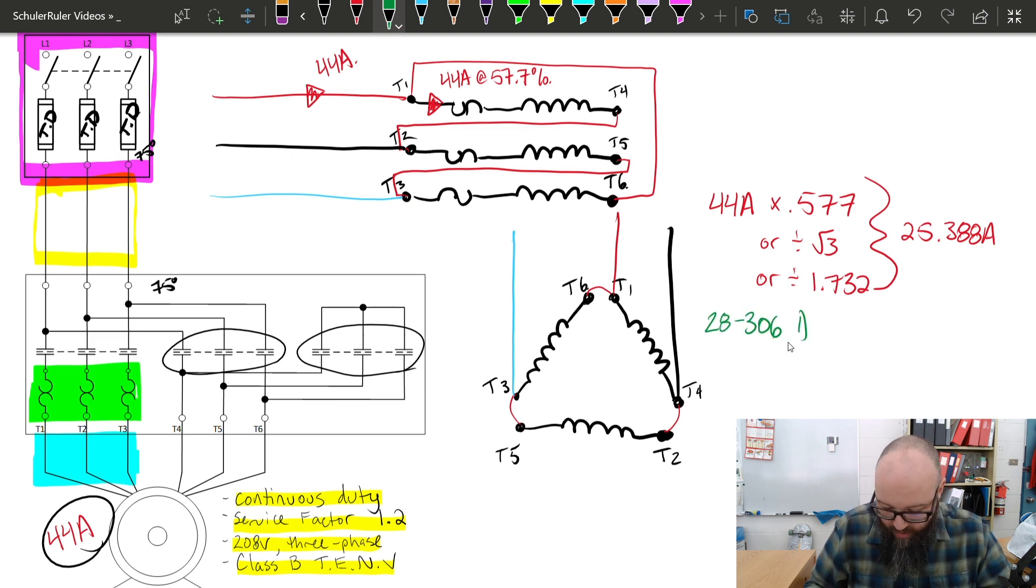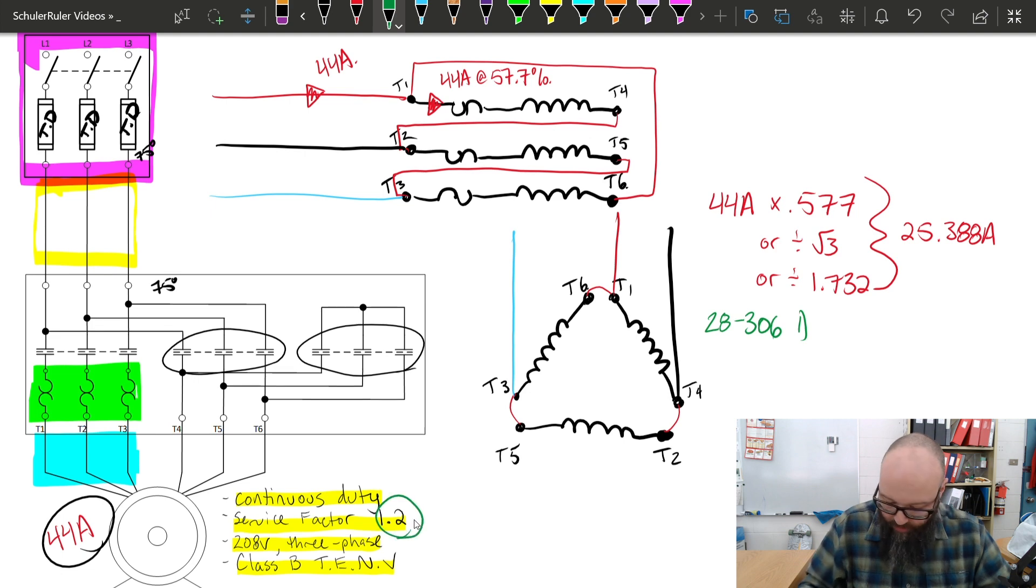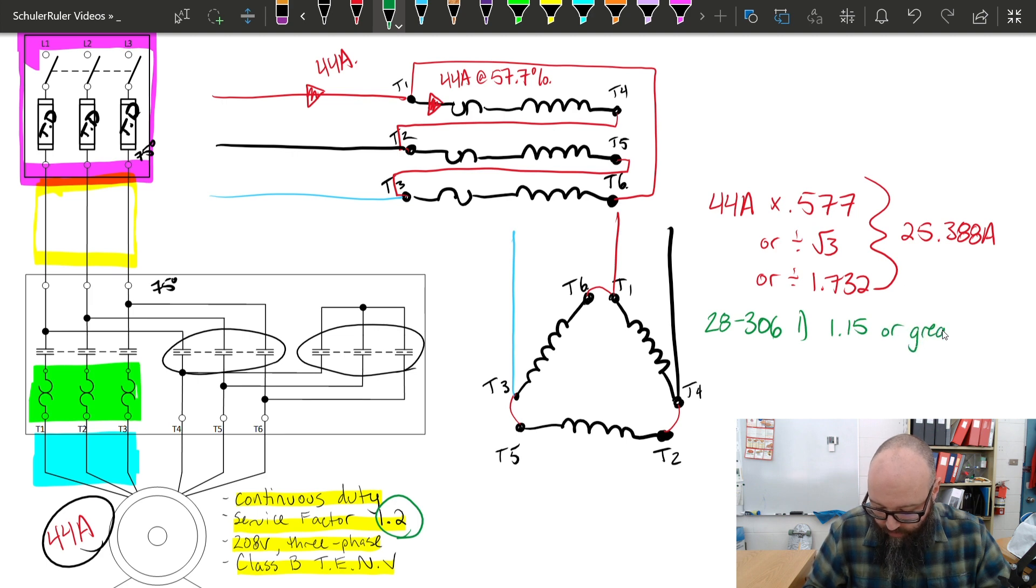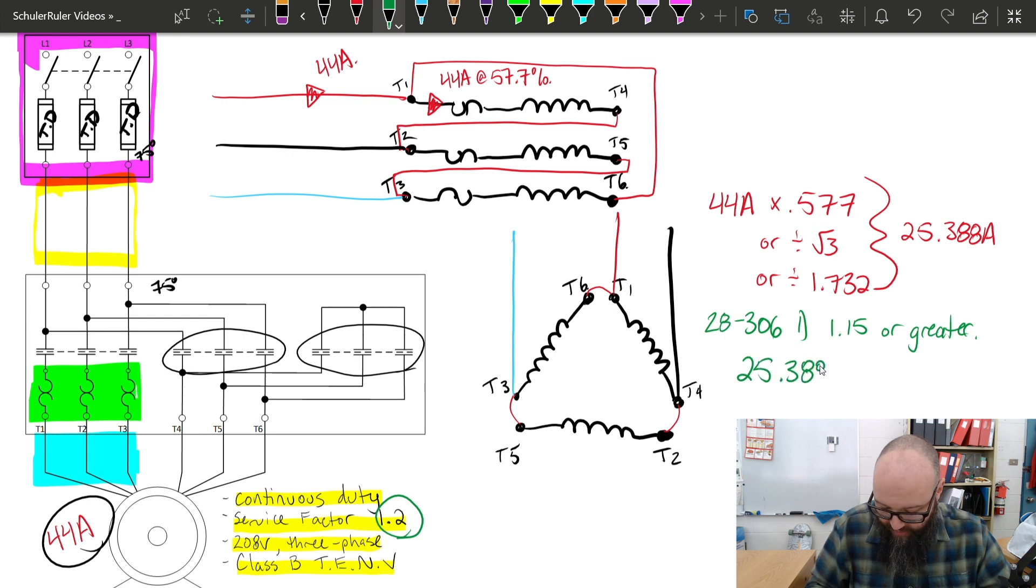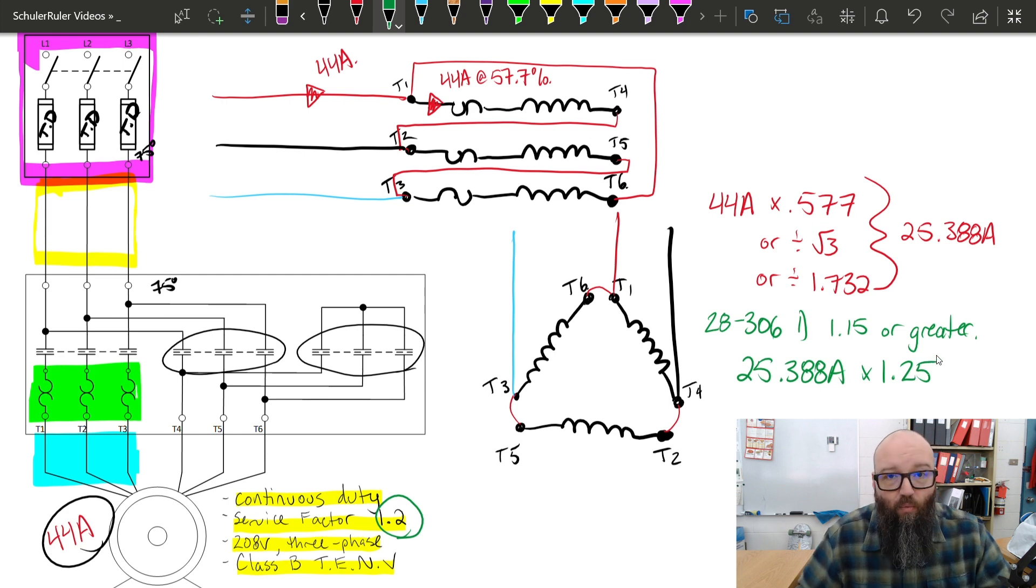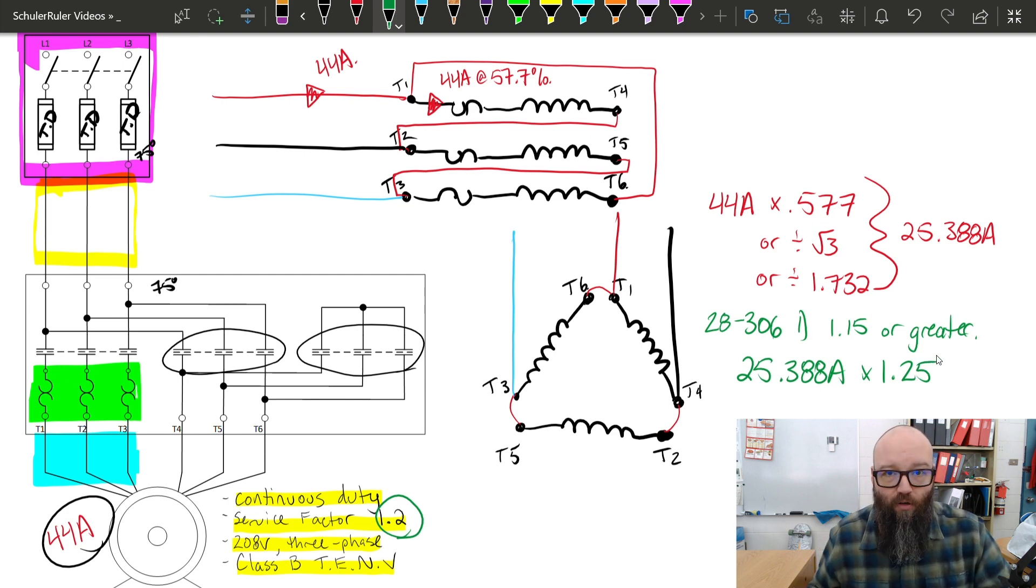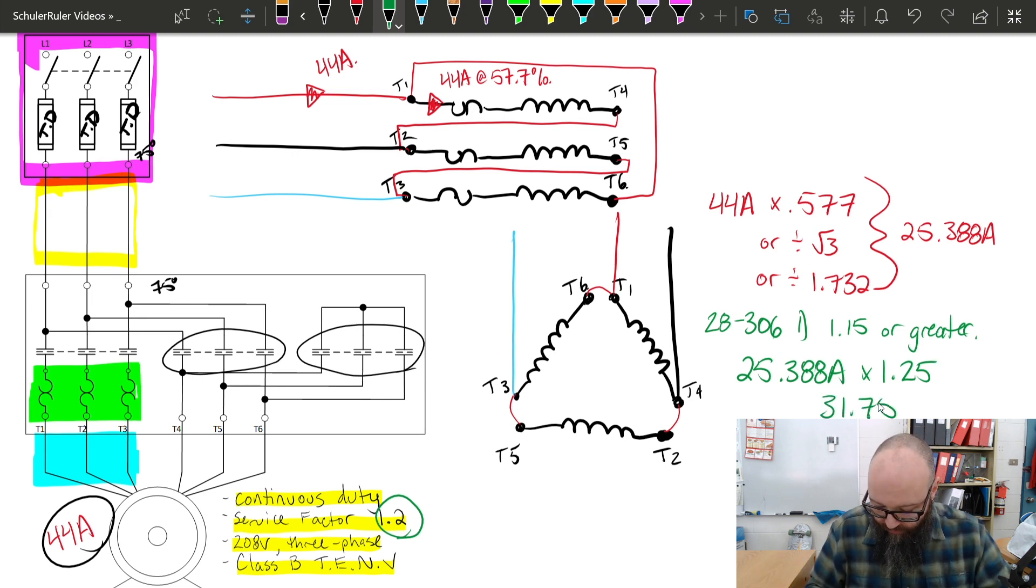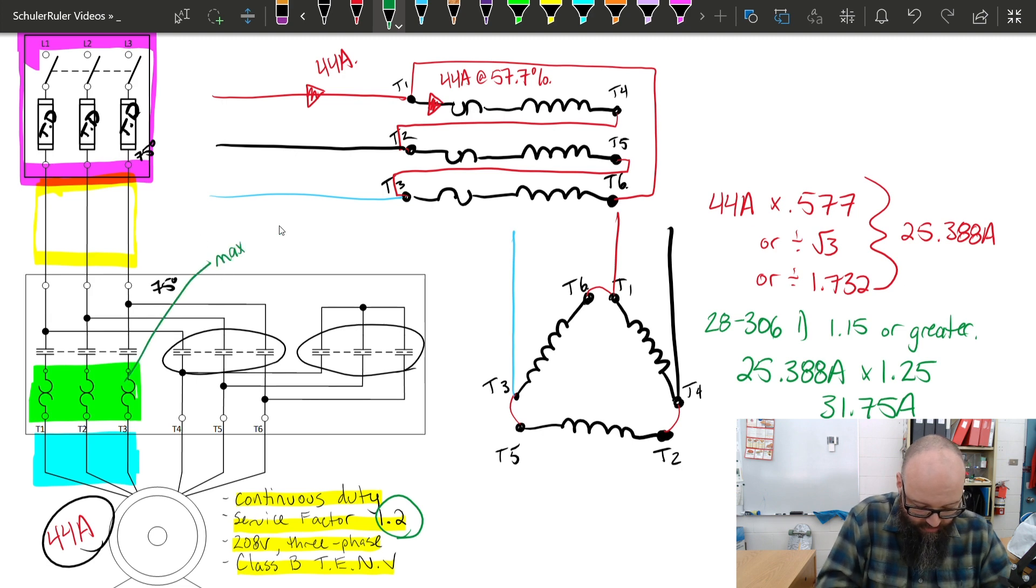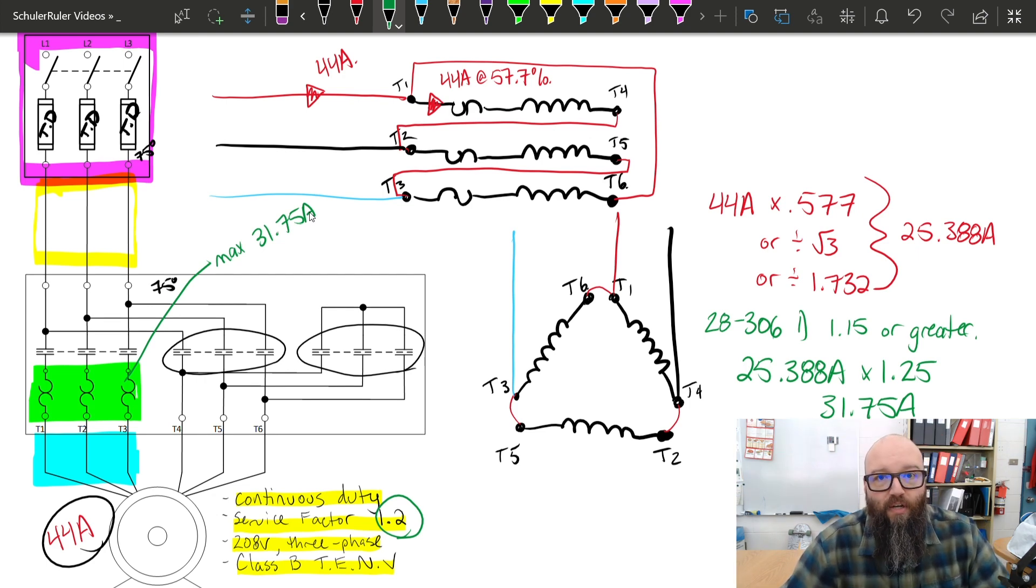Now, this is my starting point to determine the size of my overloads. This is where I'm now going to go back to 28.306 sub rule one, and I'm going to reference that service factor of 1.2, which tells me if it is 1.15 or greater, I'm going to take my 25.388 amps, and I'm going to multiply it by 1.25. What that's going to give me is the maximum trip setting of that overload heater. So, if I could dial it up, I could take it all the way up to 31.75 amps. So these overload heaters, max 31.75 amps, and that takes into consideration that phase current that those are going to experience during the run of that motor when it's in delta.